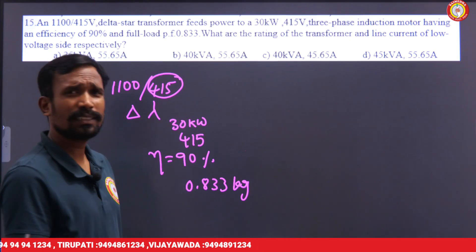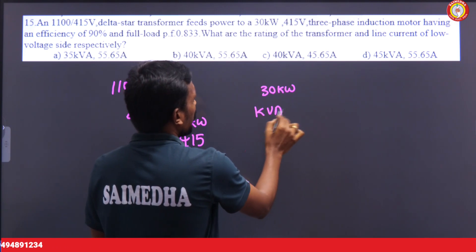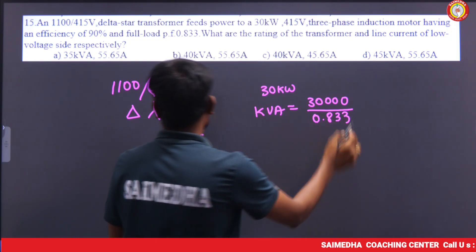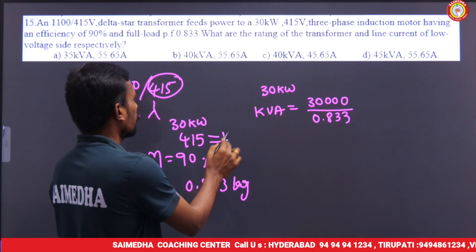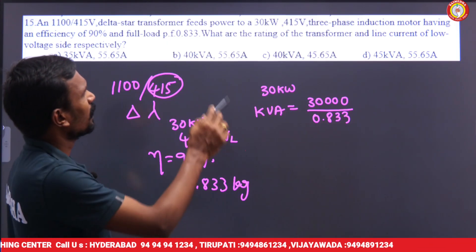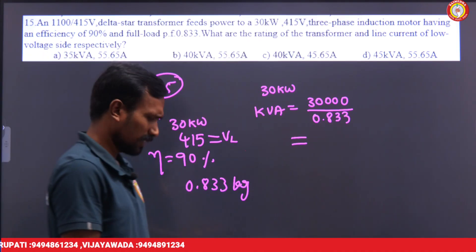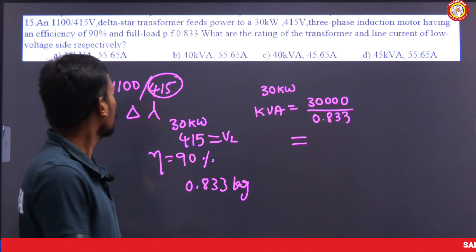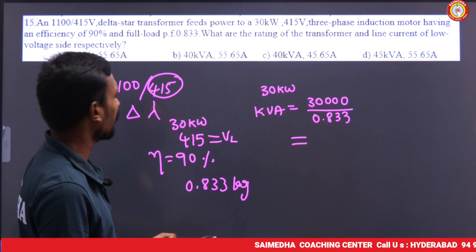The power here is 30 kilowatts. The KVA rating equals 30 kilowatts divided by power factor 0.833, and the line voltage is 415 volts. So 30,000 divided by 0.833 gives almost 36 KVA initially — but we haven't accounted for efficiency yet.